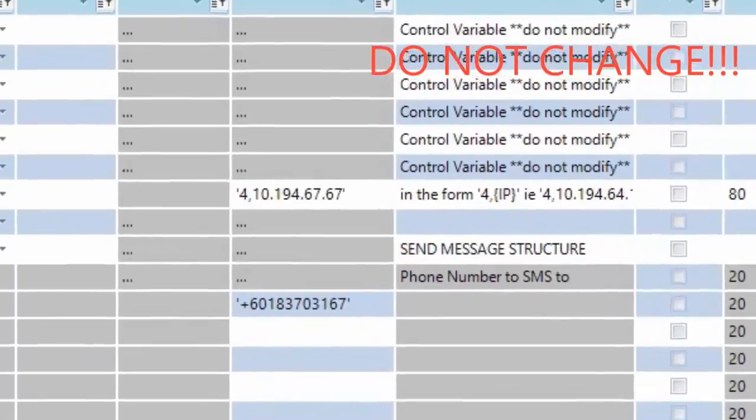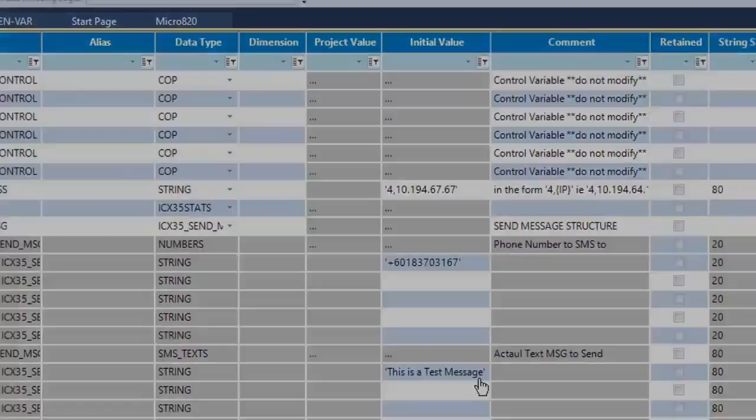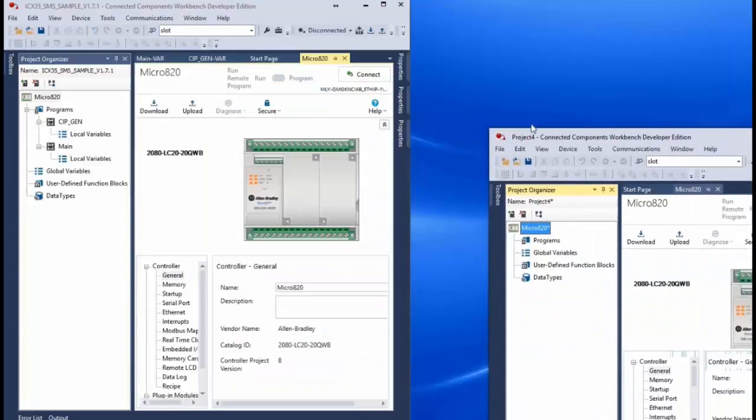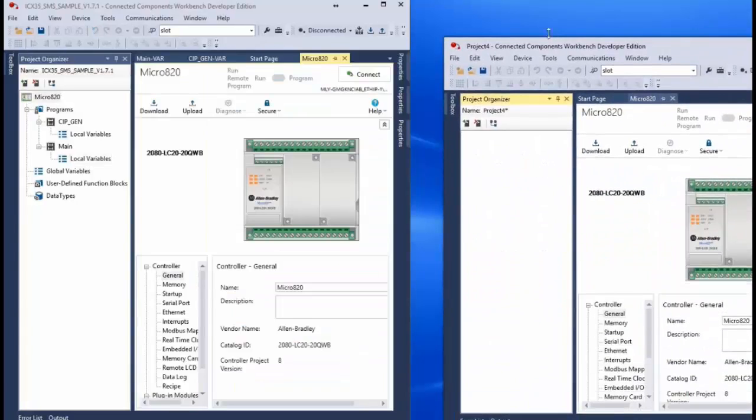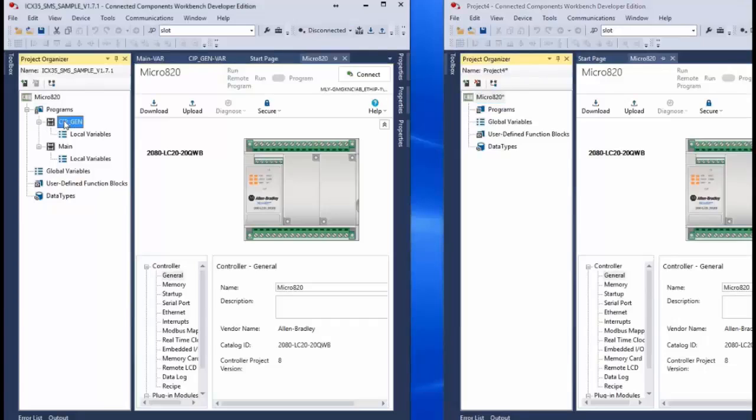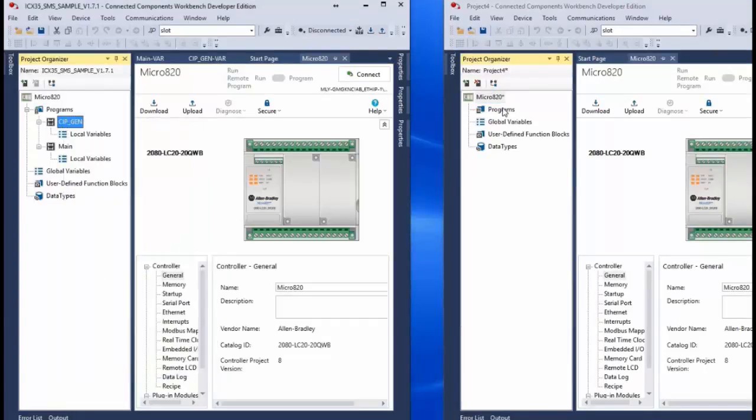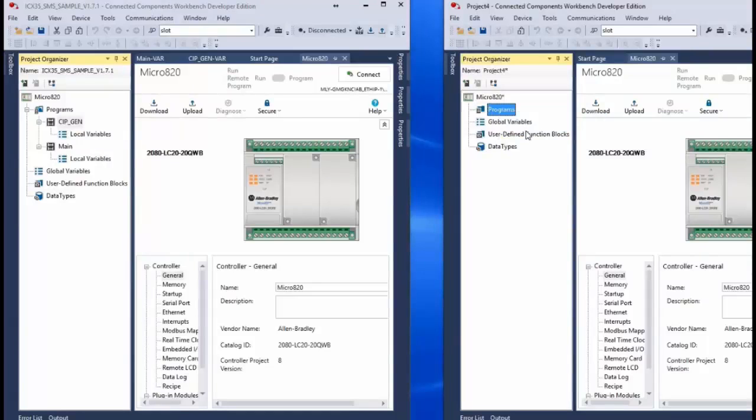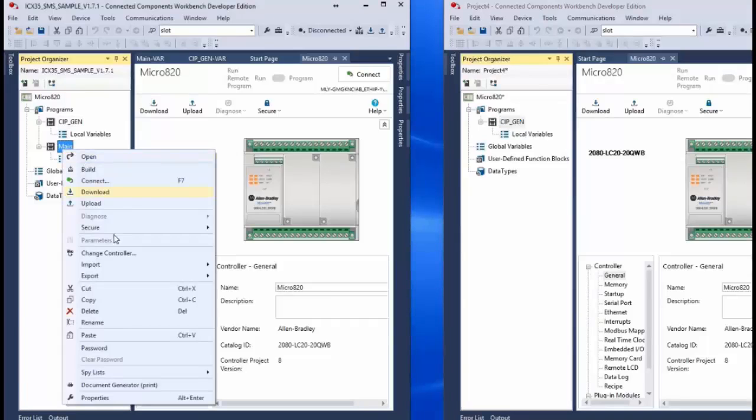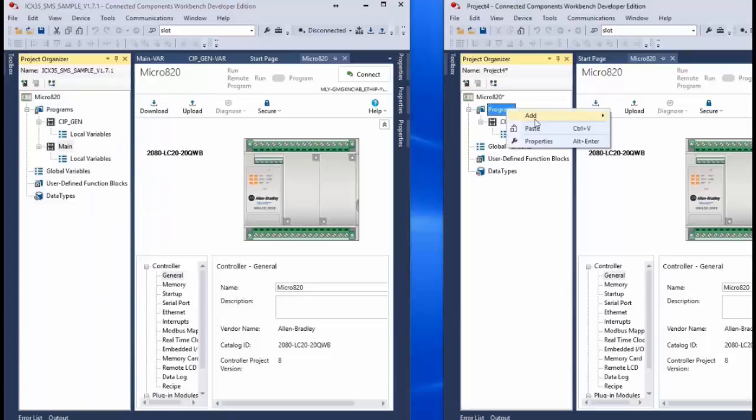Now if you have an existing CCW program that you would like to add this functionality with the ICX35 to, you can simply copy and paste the ICX35 project file into your existing logic. An easy way to do this is to just copy each of the two programs and paste them into the programs folder of your project file. This makes it easier to integrate the module's functionality into your current system. Just be sure that you do copy over both programs and that you have all the tags necessary for the normal operation of the ICX35 gateway.